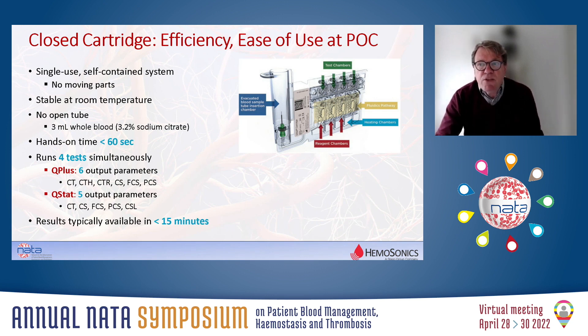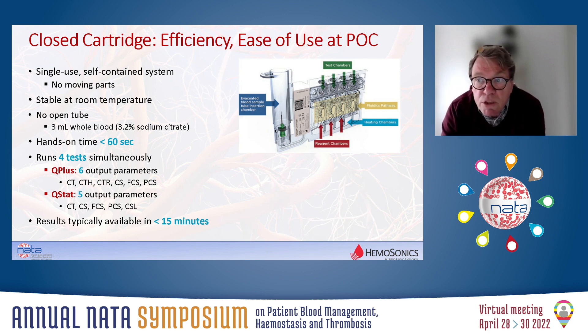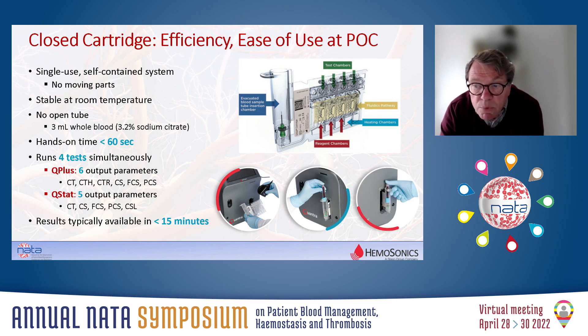All these tests and reactions are done in closed containers in cartridges. Two cartridges are available: the QPLUS cartridge with six output parameters, and the QSTAT cartridge with five parameters, which includes the fibrinolytic assessment. The cartridge contains a place to load the blood sample. Blood drawn into the cartridge is preheated, then mixed with the reagents, and finally transferred to the measurement chambers for continuous ultrasound measurement. It's a very simple operation — in less than 60 seconds the whole system is up and running. You introduce the cartridge, then introduce the sample and press start.